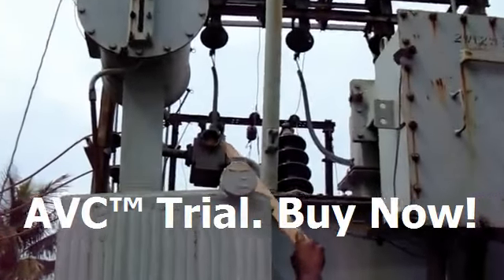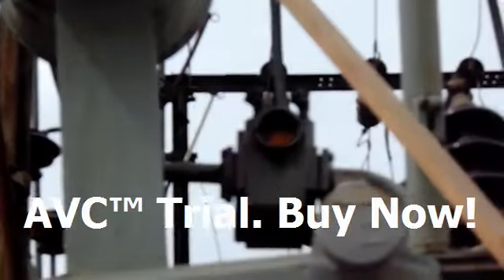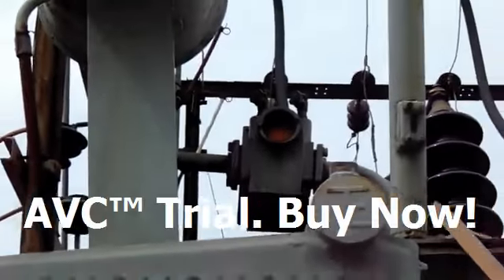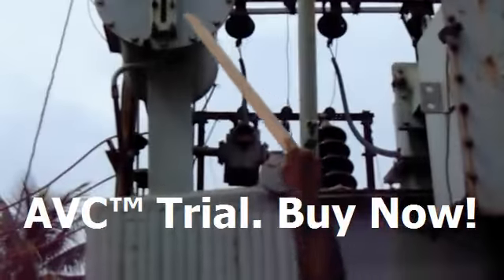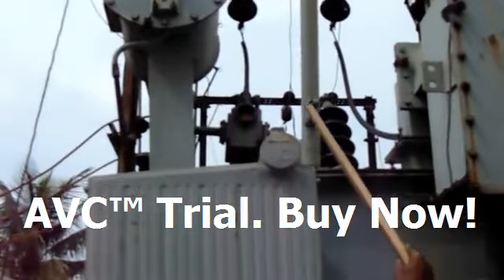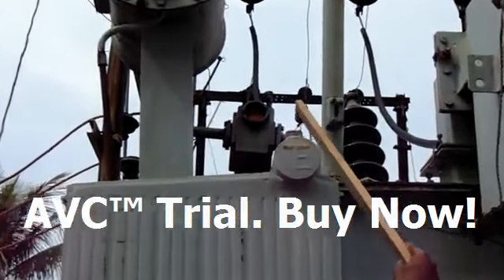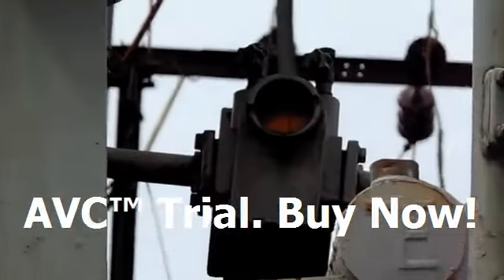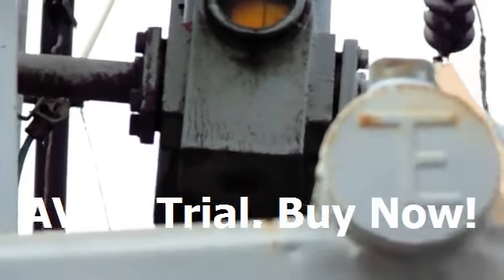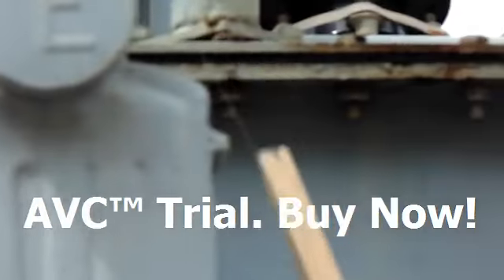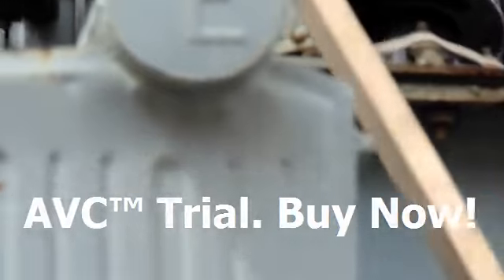There is a Buchholz relay which is connected here, between the conservator and the tank body. Between the conservator over there and the tank body, there is another device which is connected. That is the Buchholz relay. This Buchholz relay is a gas actuated relay. It acts as a protection for the transformer against any internal fault within the transformer.